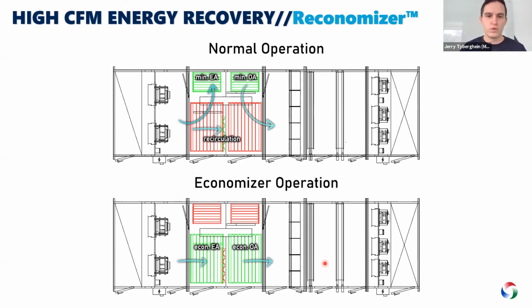So what we did was we decided, let's put a smaller wheel or plate heat exchanger in the economizer section, because you only need to be able to do 20 to 25% OA. So this is a return fan, and it goes through the wheel here and exhausts out up top. Outside air comes in from the top, goes through this filter bank and through the wheel, and then in the supply air stream. And then you have a recirculation damper too.